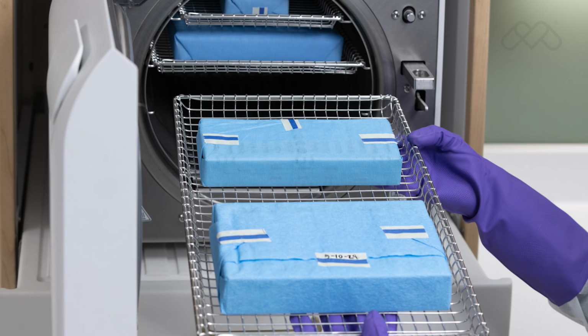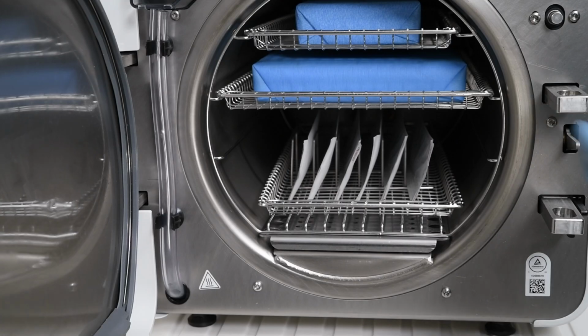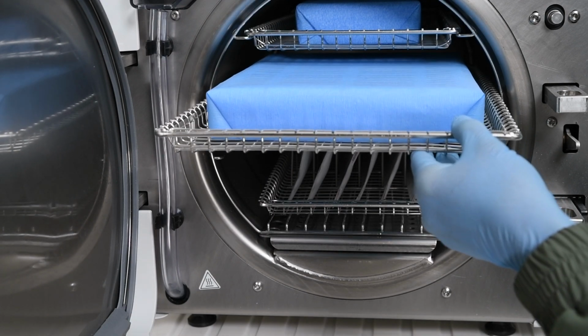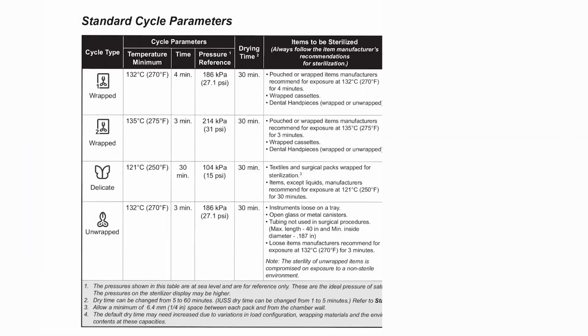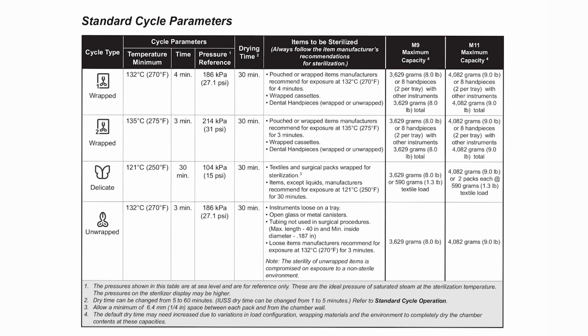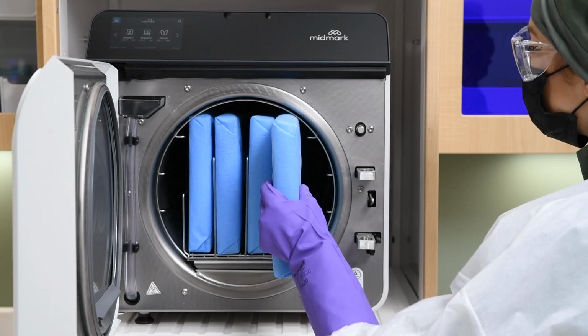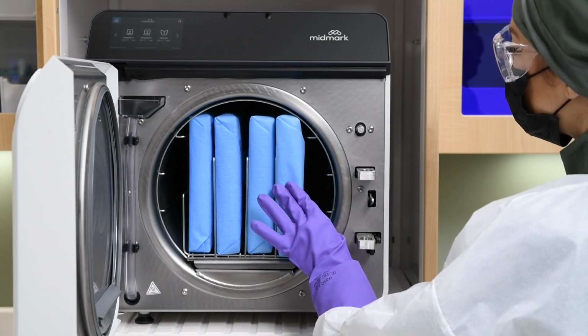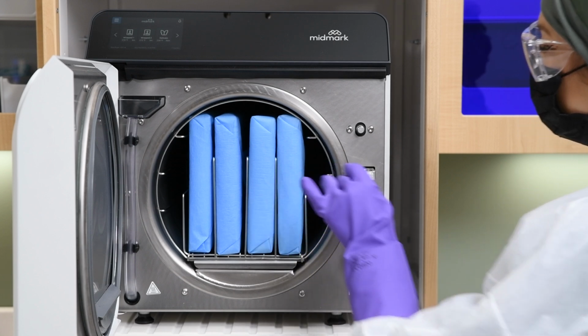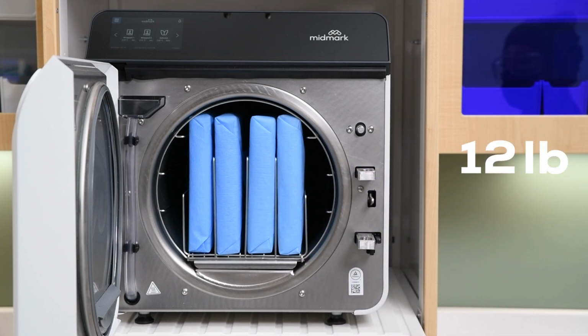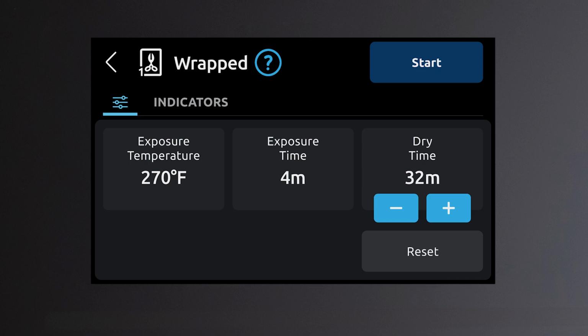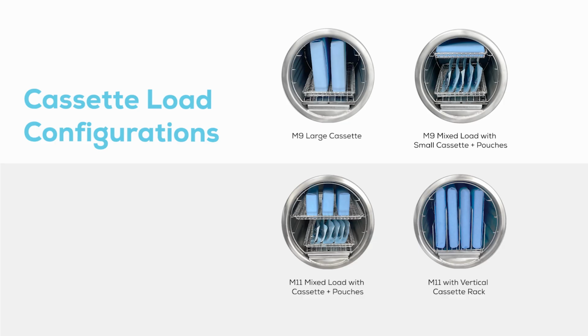Cassettes can be loaded on the trays, but they must fit within the boundaries of the tray and they should not touch each other, the tray above, or the chamber wall to allow proper steam circulation. The total instrument load, including the cassettes, should not exceed the limits listed in the maximum capacity tables in the setup and user guide. When using the optional vertical cassette rack in the M11, the maximum load including cassettes can be increased to 12 pounds. Additional dry time may be required. Shown here are some recommended cassette load configurations.